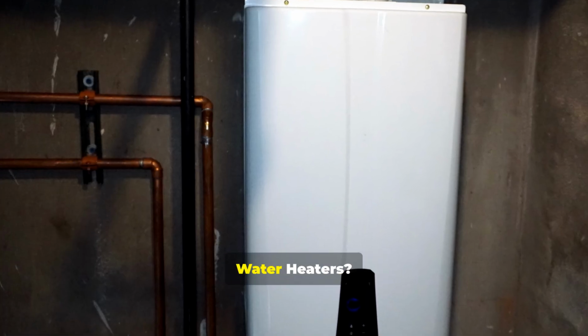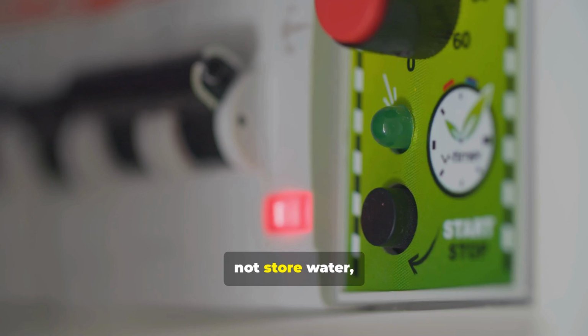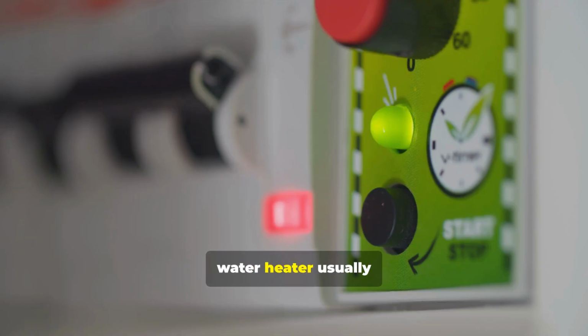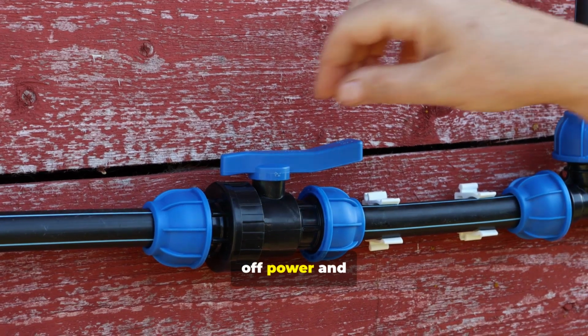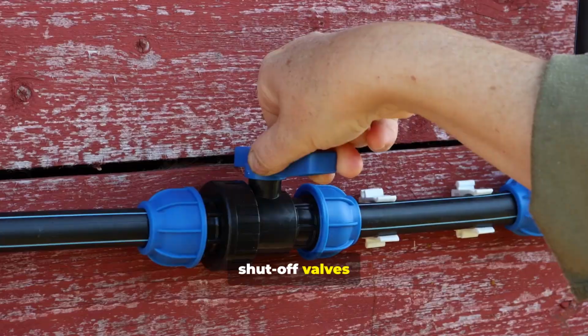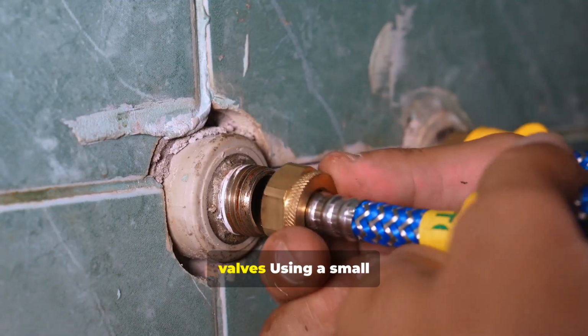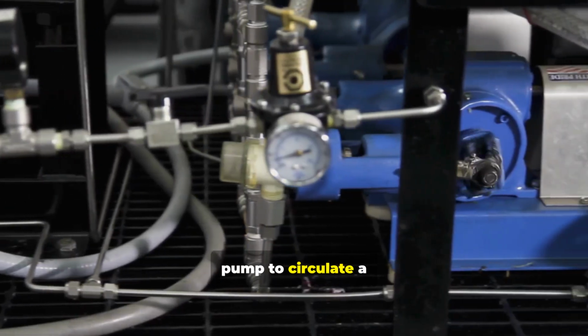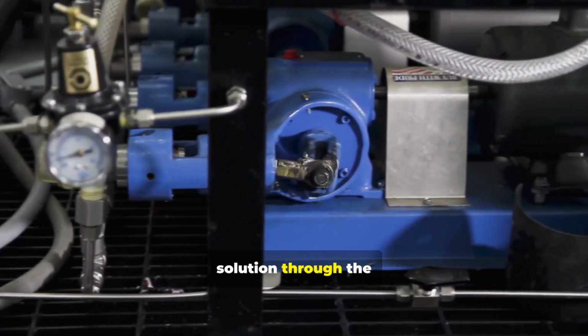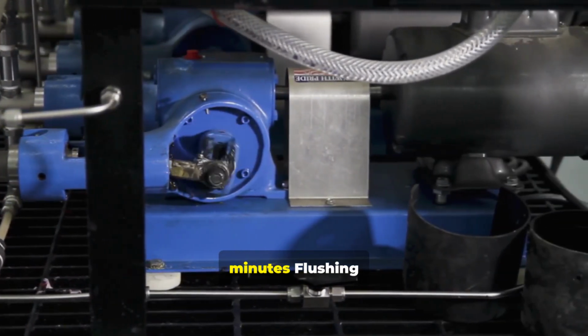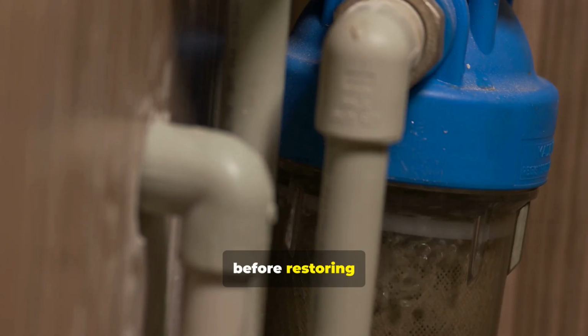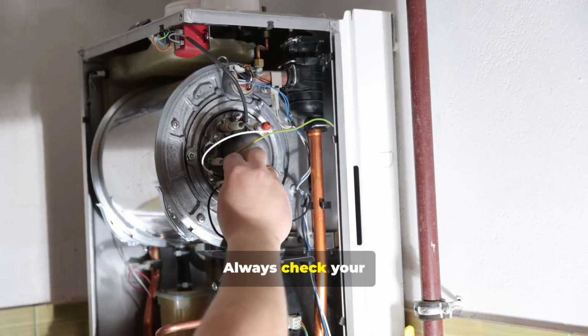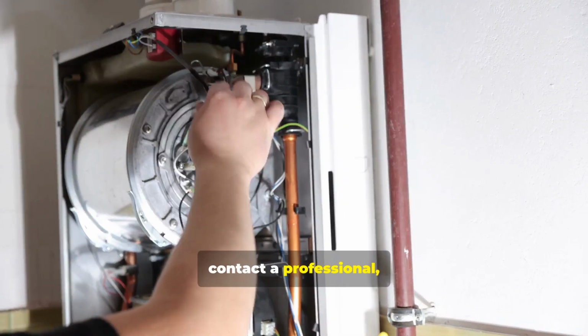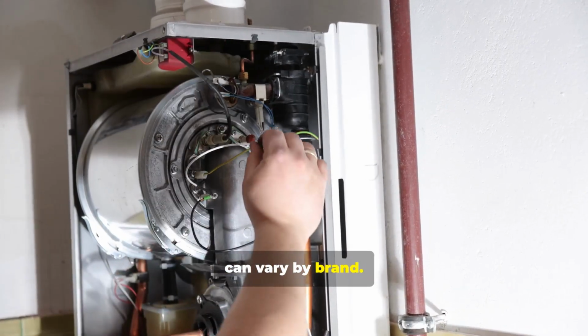What about tankless water heaters? Tankless models do not store water, but they still need maintenance to prevent mineral buildup inside the heat exchanger. Cleaning a tankless water heater usually involves turning off power and closing water shutoff valves, connecting hoses to the service flush valves, using a small pump to circulate a vinegar or descaling solution through the system for 30 to 45 minutes, flushing with clean water before restoring power and use. Always check your owner's manual or contact a professional, since the process can vary by brand.